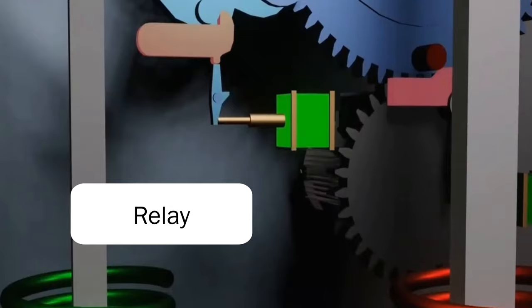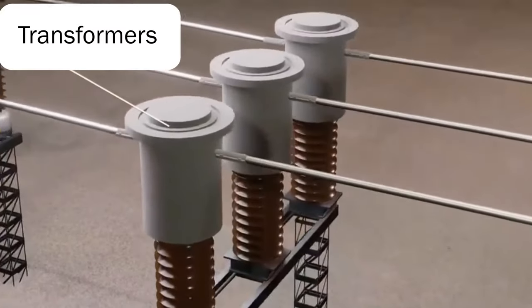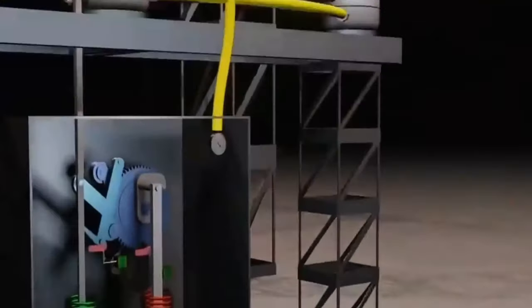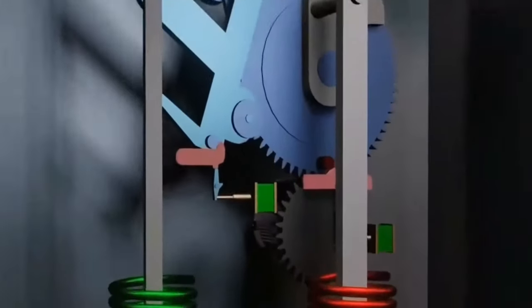Near the circuit breaker, there are also some current transformers. When there is a problem in the circuit, the current in the transformers increases, and they send the abnormal situation to the relay. This is when the plunger of the relay extends outward, releasing the latch.